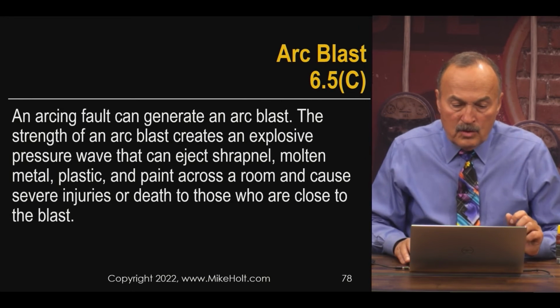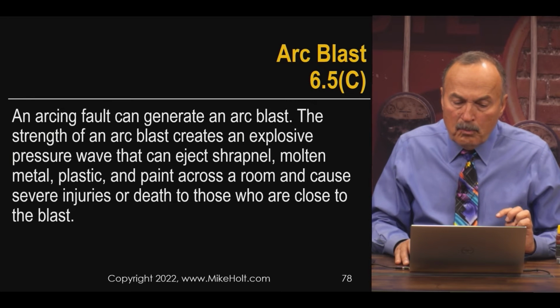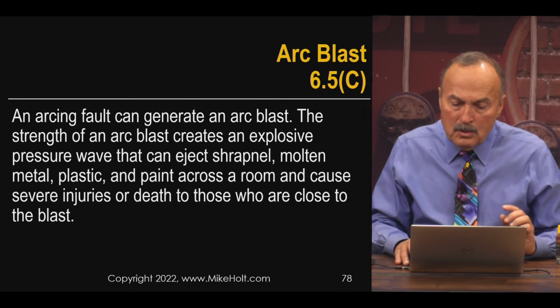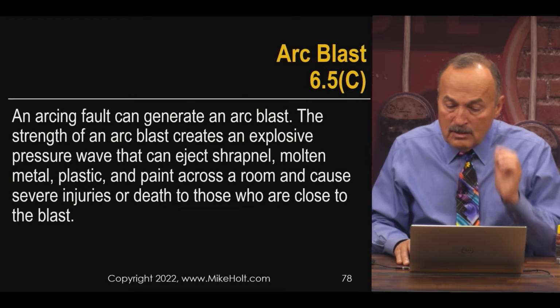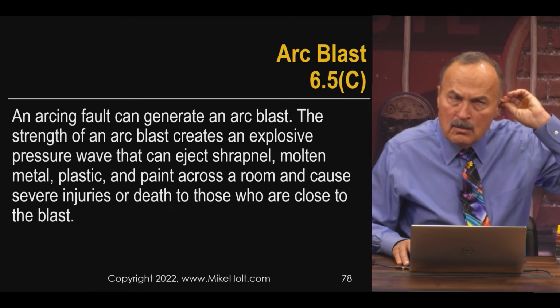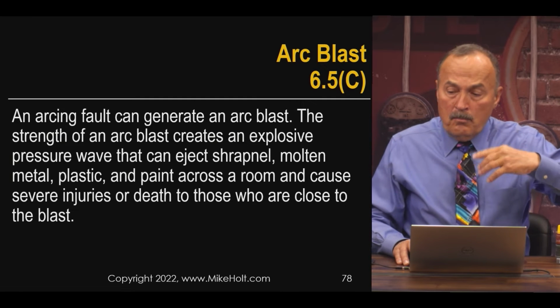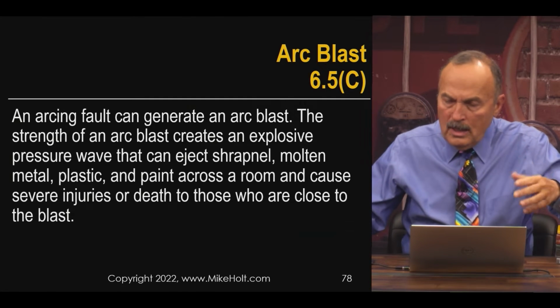The strength of the arc blast creates an explosive pressure wave that can eject shrapnel, molten metal, plastic, paint across the room and cause severe injuries or death to persons close to the blast. So we not only have heat that could cause a second degree burn, we have heat that could ignite clothing that was never intended to be at that temperature.